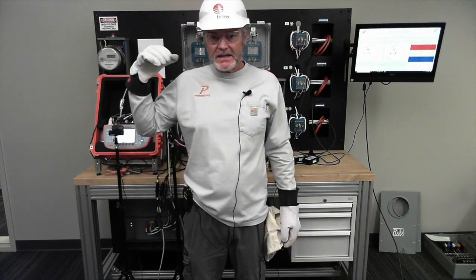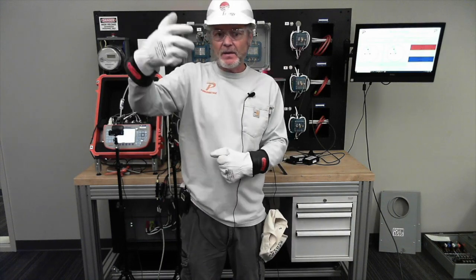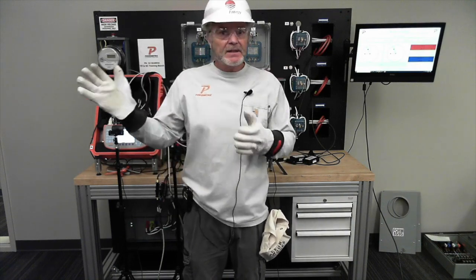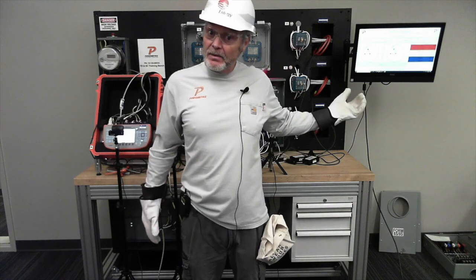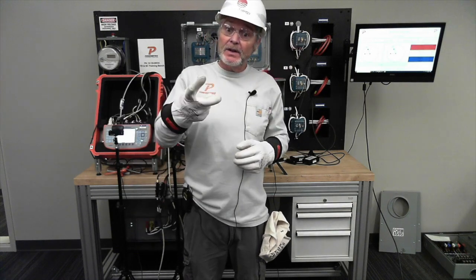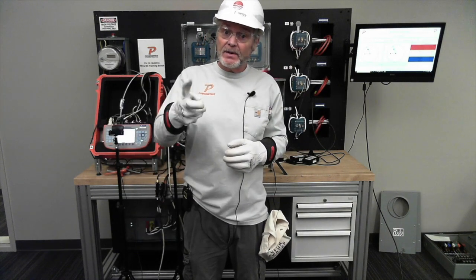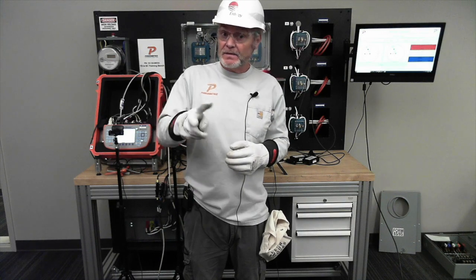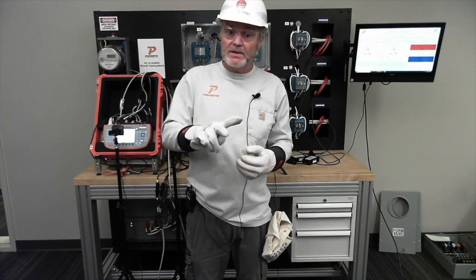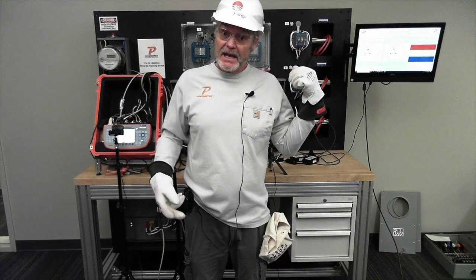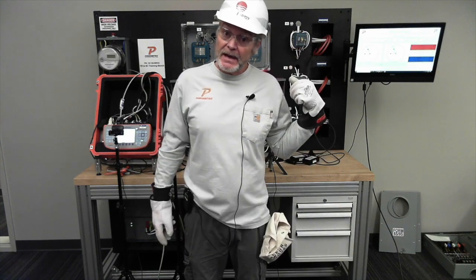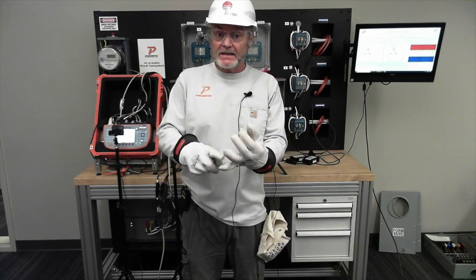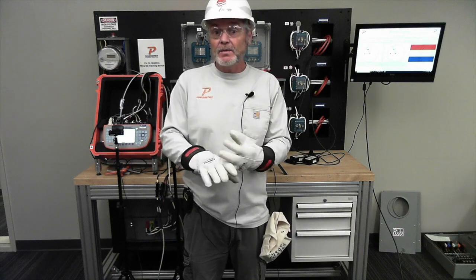If you had gone to this site and tested, you'd have passed on the meter, passed on the CTs, and moved to the next one. But it's not really correct, is it? That's why you should double check your primary versus your secondary when looking at those sets of vectors. You can toggle between those two tabs and take a look. In this case, there definitely is a problem that needs to be corrected. But just testing on that secondary side, testing those CTs and that meter, you wouldn't see it.